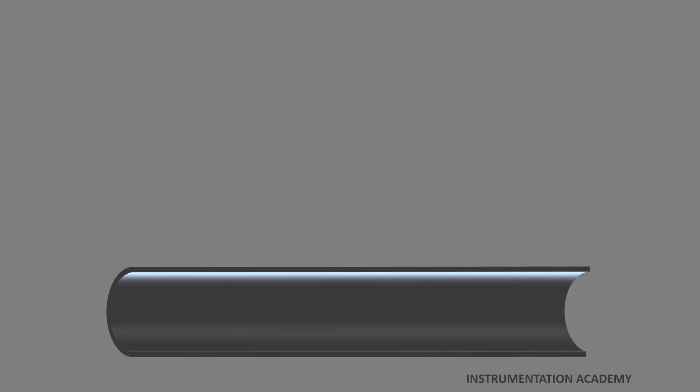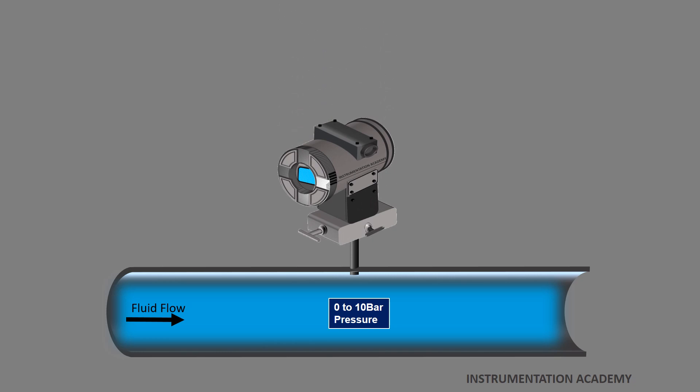Let's consider that a fluid passing through a pipeline exerts a pressure in the range of 0 to 10 bar. A pressure transmitter is connected which is calibrated to generate a current signal in the range of 4 to 20 mA which is proportional to the pressure being exerted by the fluid on the pressure sensor.